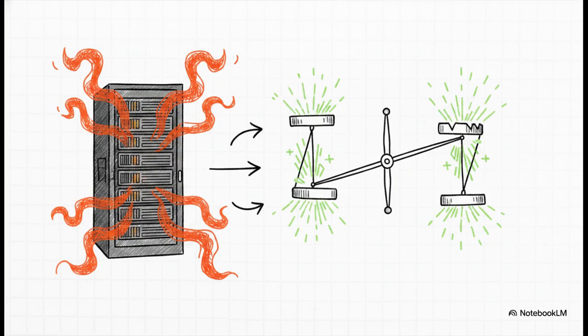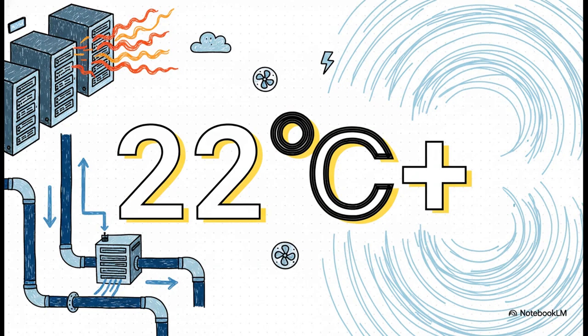As we wrap up this explainer, there is a fascinating paradox happening right now, driven entirely by the high-density nature of modern AI. You see, hotter running high-density AI servers are completely changing the baseline rules of cooling efficiency. Because AI servers run so hot, the target temperature for the chilled water they need has actually shifted. Historically, chillers had to output water at a chilly 7 to 12 degrees Celsius. But today, for these new setups, that requirement has increased to 15 or even 22 degrees Celsius and beyond.